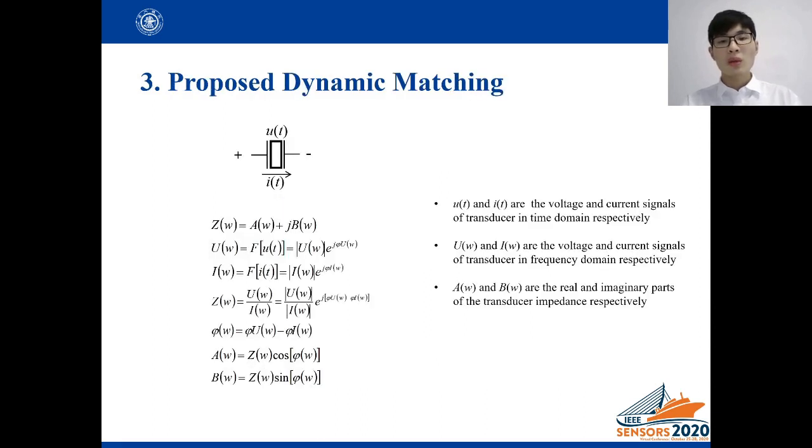In order to address this problem, we have to measure the transducer impedance in real time. So the voltage signal and the current signal of transducer must be measured.